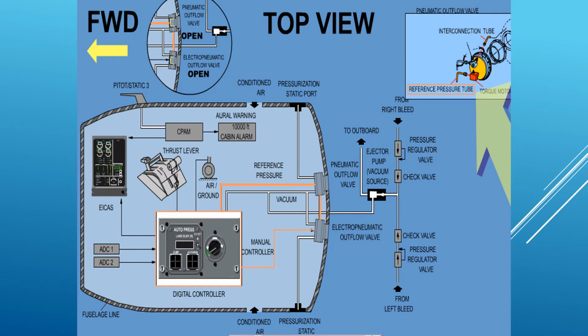The other thing to point out, if there's a failure with the automatic mode, it's quite possible there will be a fault code displayed in the landing elevation window, which is good. The bad news is, when you go to manual mode, that display disappears, and along with the code. So the crew hopefully will have made a note of that fault code, because once they go to manual mode, it's lost. So a bit of a flaw in the system design there. But that's the pressurization system.